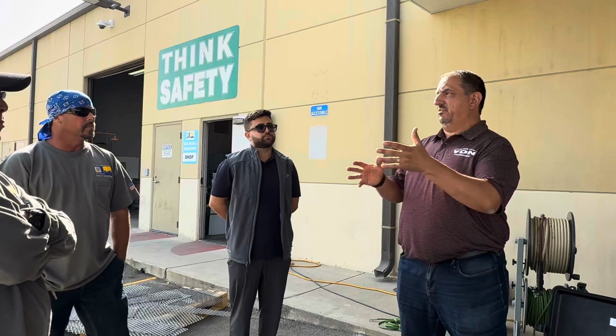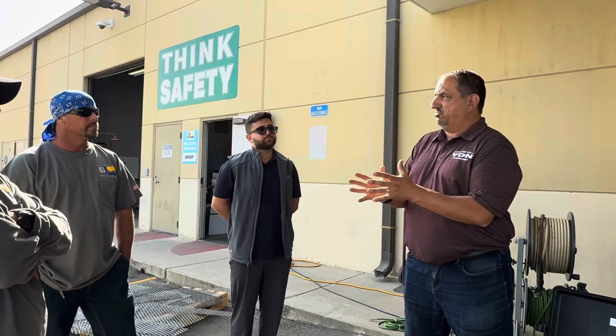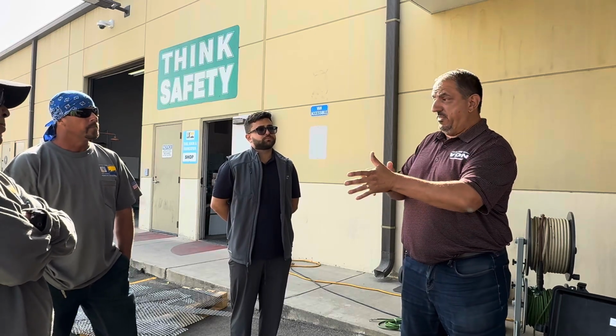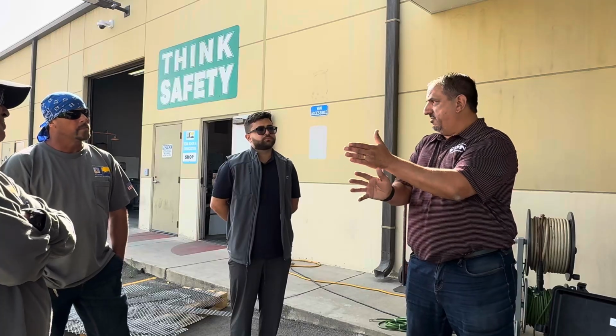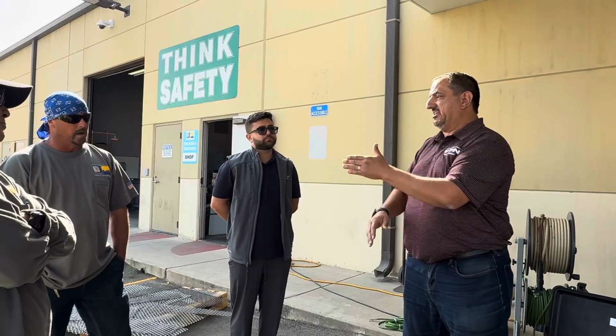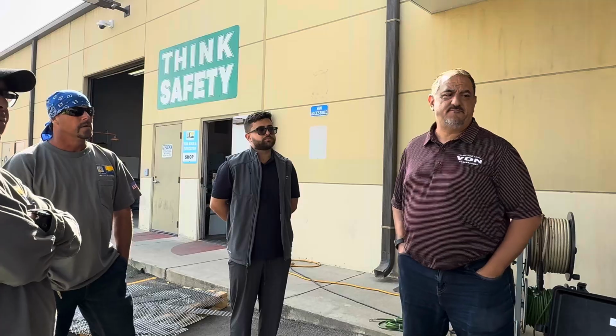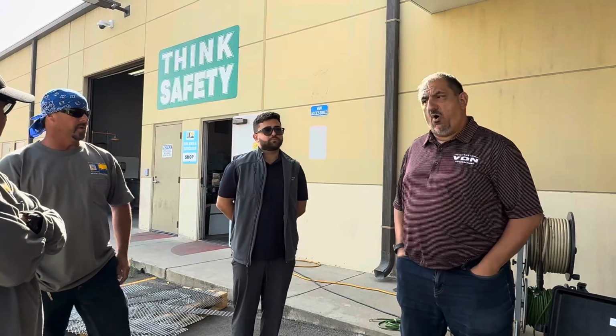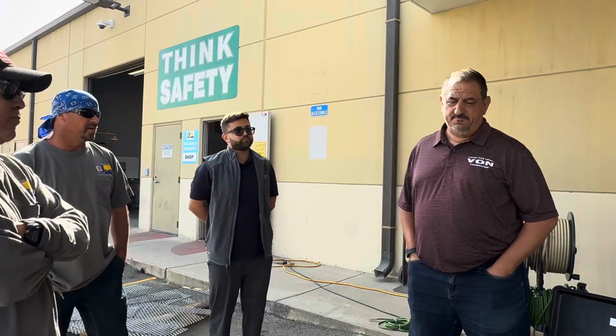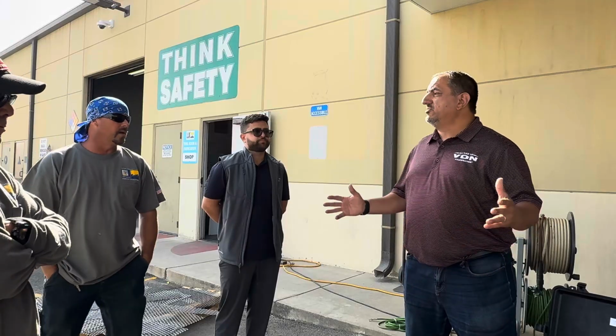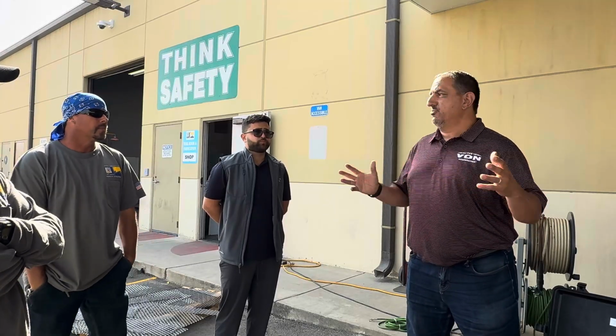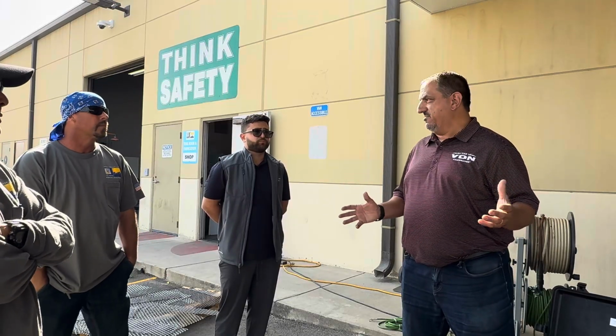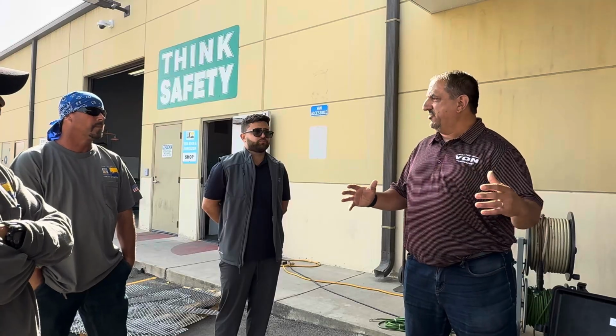I've seen where sometimes in those transformers it's so tight where they'll use a feed-through in there and they're still putting a blanket right next to it because it's right next to the other cable. So you got to be careful, because it could snap over—you want something covering the end. At least from what I've seen, newer transformers isn't really the case like that anymore; there seems to be a little bit more space in there to do that.